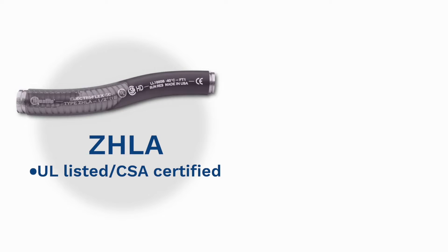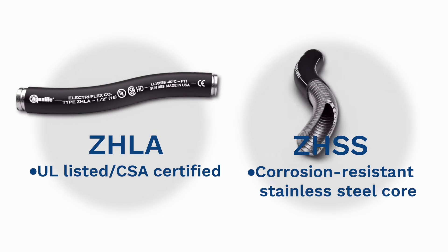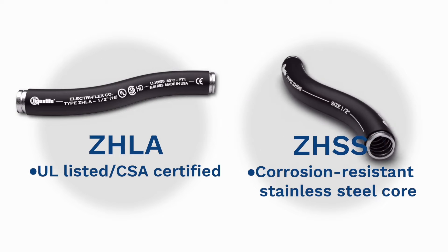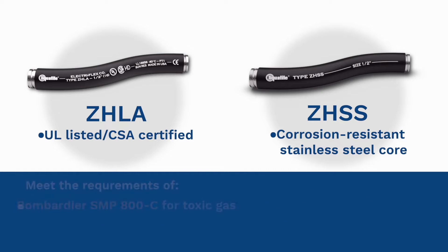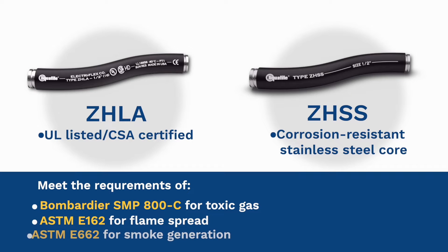Rail, transit, and infrastructure applications have unique challenges. These applications require a resilient polyurethane jacket that is also compatible with common oils and chemicals. And because passenger safety is always the main concern, conduit jacketing should be zero halogen, providing a low fire hazard solution. The ZHLA and ZHSS conduits are ideal and meet the requirements of Bombardier SMP 800C for toxic gas generation, ASTM E162 for flame spread, and ASTM E662 for smoke generation.